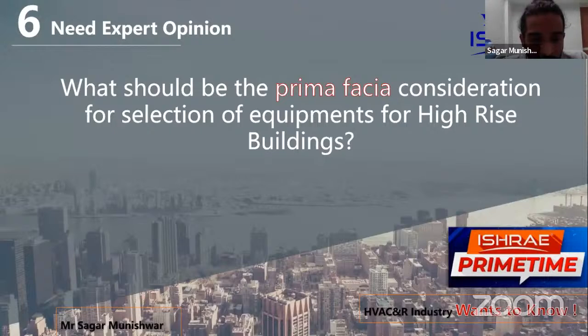As far as pumps are concerned, no issues. Of course, as I mentioned, as you go high rise, it's a good design practice to have an intermediate break pressure system where you have pumps installed on various floors, which can help reduce the pressure on the pumps. And the third aspect is how you select the piping and how you select the valves. You must have read a lot of ISHRAE journals which talk about a reverse return piping system vis-a-vis pressure independent balancing control valves. In a chilled water system, what is important when you go high rise is you need to have an equal pressure drop across each AHU and equal pressure drop across each FCU. Now that can be attained by either reverse return piping or a pressure independent balancing control valve.